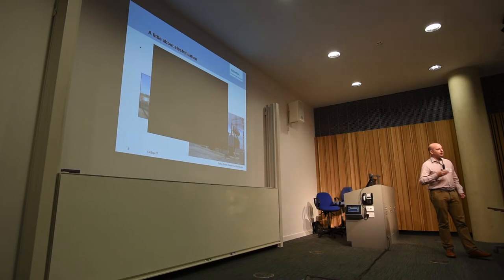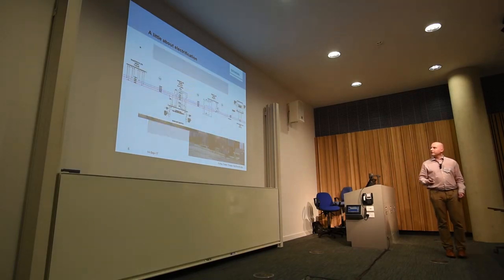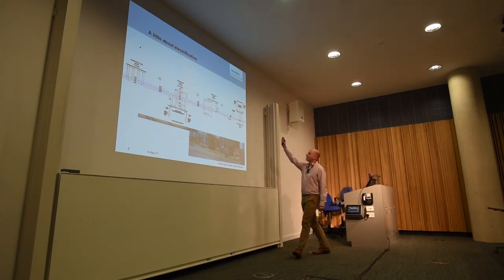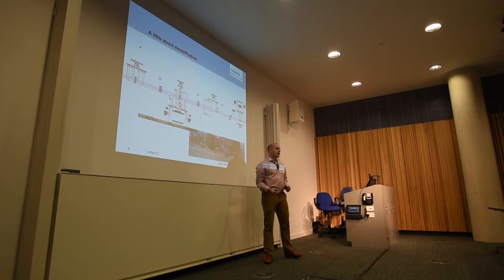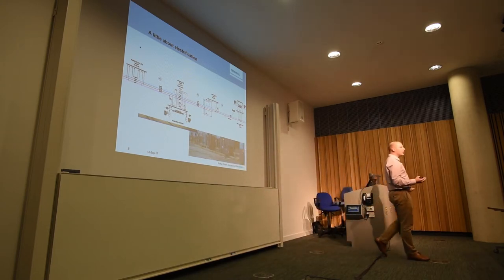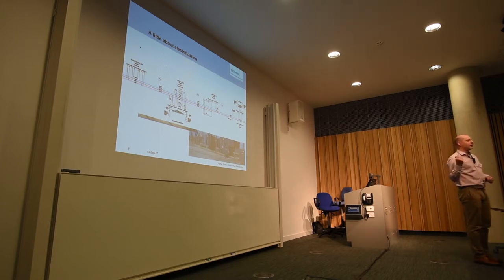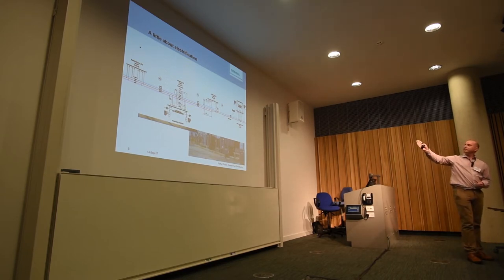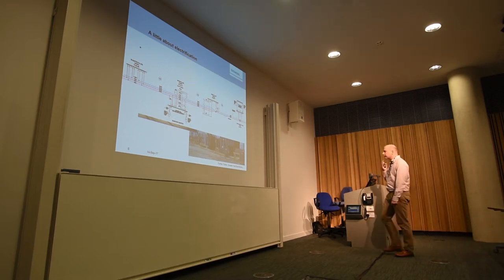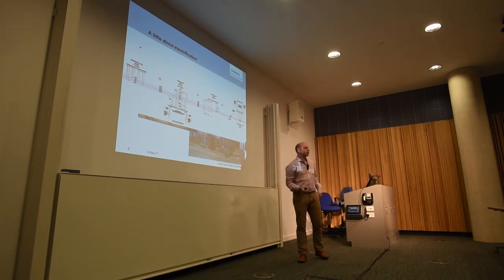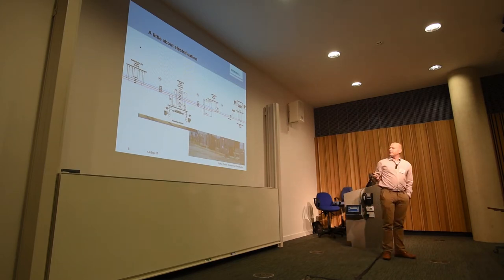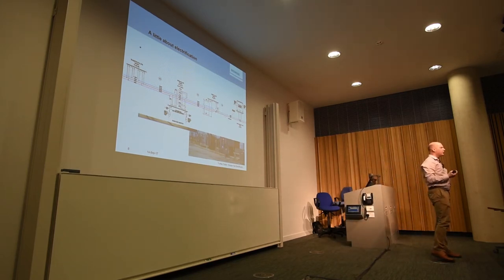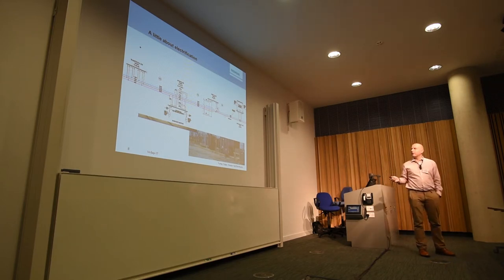So we then have to run our own medium voltage three-phase system to supply power to these individual substations. This is a typical major feeding diagram. You'll see there are two supply points here, each with two transformers, and each of those transformers sits on different phase pairs. So in principle they should balance the unbalanced effect of taking current from just two conductors at each individual transformer. In between you have neutral sections, those black rectangles, which separate the different feeding areas of the railway. Just in terms of scale, you're talking roughly 10 to 15 kilometres between each substation. Typical supplies, you're talking 10 MVA up to 80 MVA, the biggest supplies, at each of these supply points.